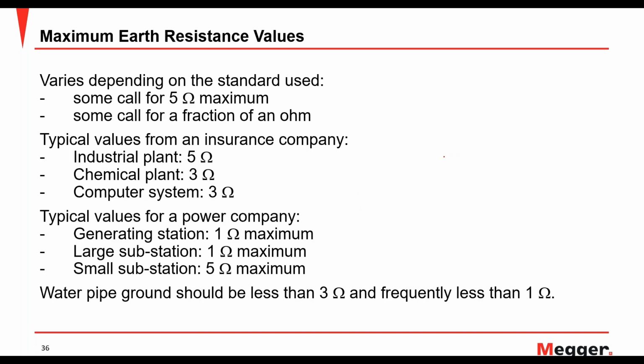What are the typical good values for a good ground system? Some call for 5 ohms maximum, that is, nothing more than 5 ohms for a grounding rod, or a fraction of an ohm. A fraction of an ohm, anything less than 1 ohm, is considered to be good. Typical values from an insurance company point of view: for an industrial plant, nothing more than 5 ohms, chemical plant 3, and computer system 3. And typical values for a power company or utilities, nothing more than 1 ohm for generating stations and large substations, while small ones may be permissible up to 5 ohms. So these are your typical good ground values. A lot of the time we get asked in the field what do I consider good and bad? So this is a good reference to keep in mind.